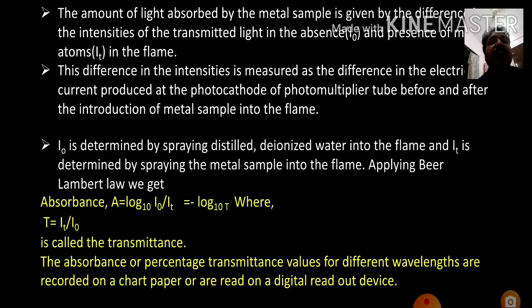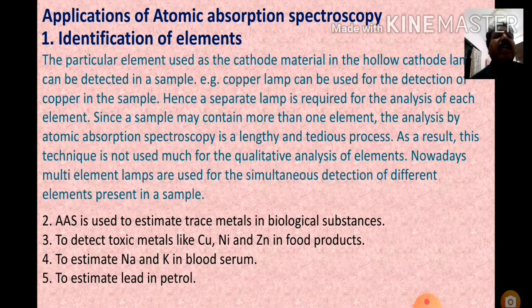Now let us see applications of atomic absorption spectroscopy. The first application is qualitative analysis. Qualitative analysis includes identification of the elements. The particular element used as the cathode material in the hollow cathode lamp can be detected in a sample. For example, a copper lamp can be used for the detection of copper in the sample. Hence, a separate lamp is required for the analysis of each element.